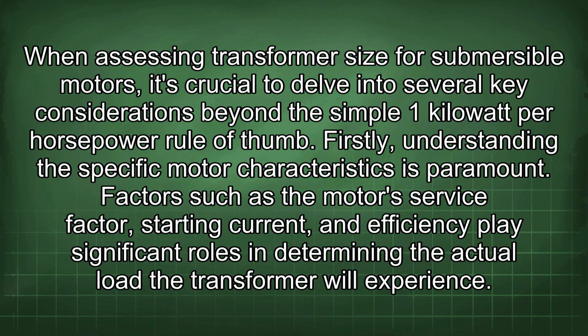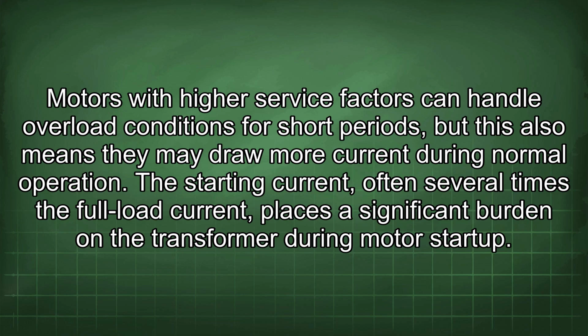When assessing transformer size for submersible motors, it's crucial to delve into several key considerations beyond the simple 1 kilowatt per horsepower rule of thumb. Firstly, understanding the specific motor characteristics is paramount. Factors such as the motor's service factor, starting current, and efficiency play significant roles in determining the actual load the transformer will experience. Motors with higher service factors can handle overload conditions for short periods, but this also means they may draw more current during normal operation.